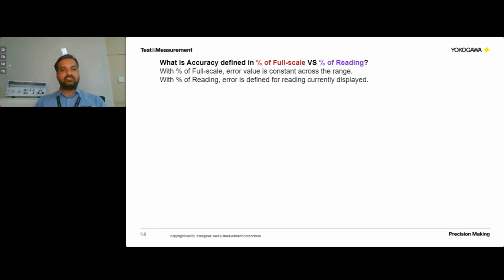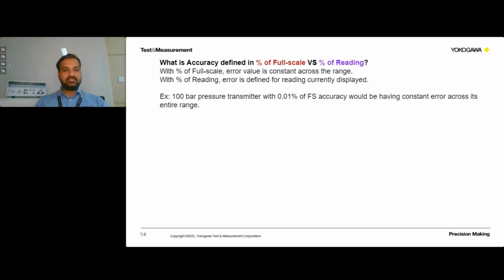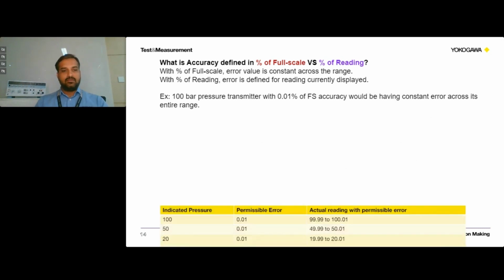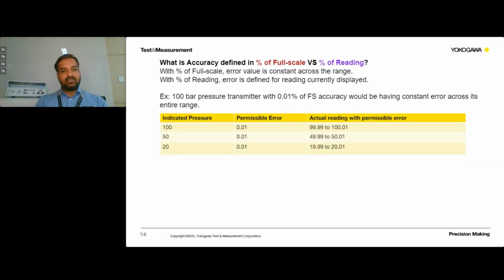So we'll see what are the advantages of having a percentage of reading and what are the disadvantages of having a percentage of full scale. Both are effective, but we'll see how it makes a difference to the measurement. For example, we'll consider a pressure transmitter of 100 bar range, which has 0.01% of full scale accuracy. Even if in the 100 bar range we are measuring lower values such as 20 bar and 50 bar, our permissible error is going to remain constant. 0.01 will be the constant error across the range. Even if you are measuring 20 bar, the error is 0.01. Even if you are measuring 50 bar, the error is 0.01.